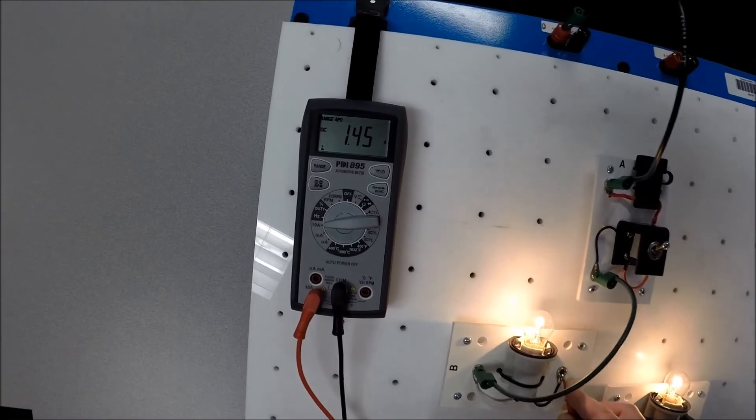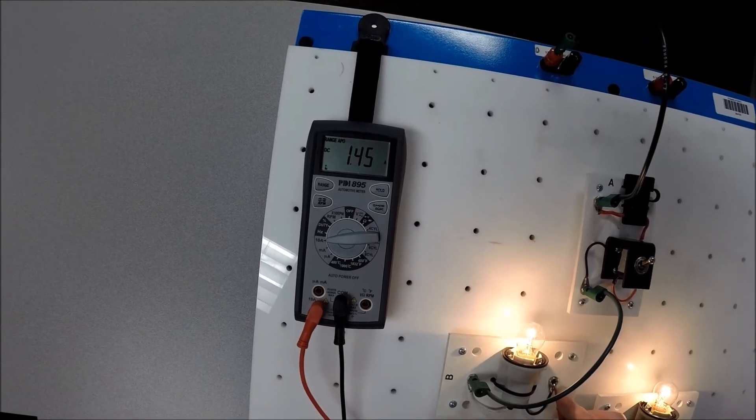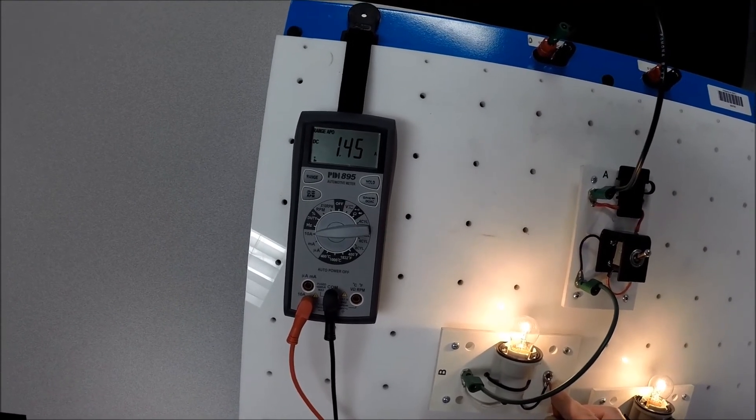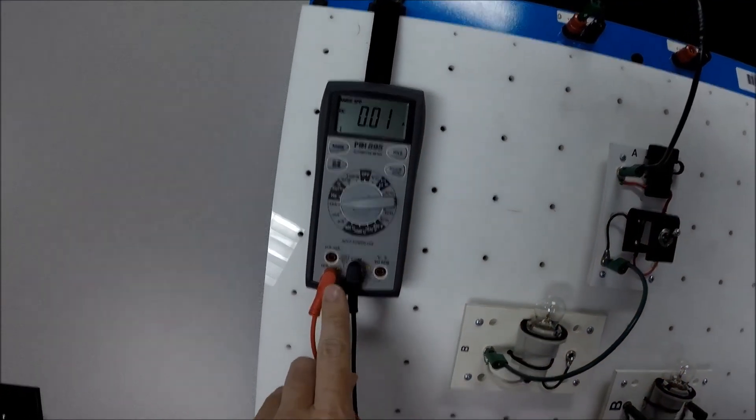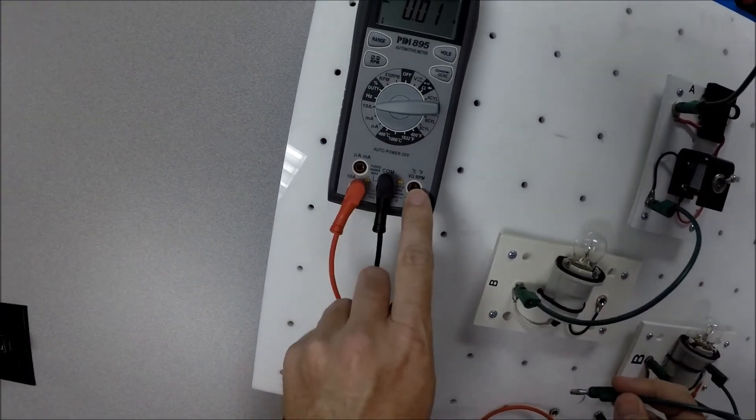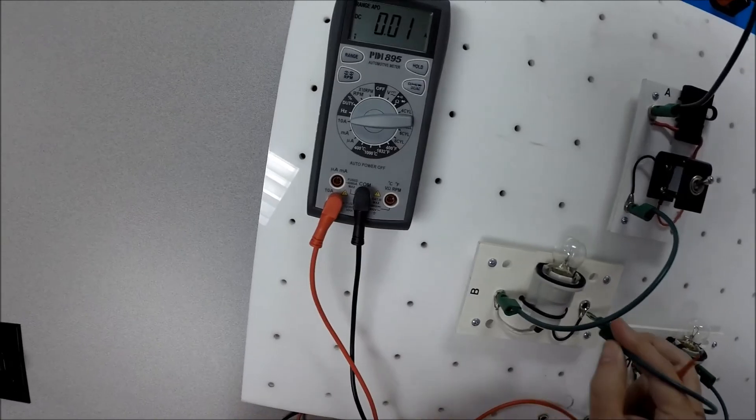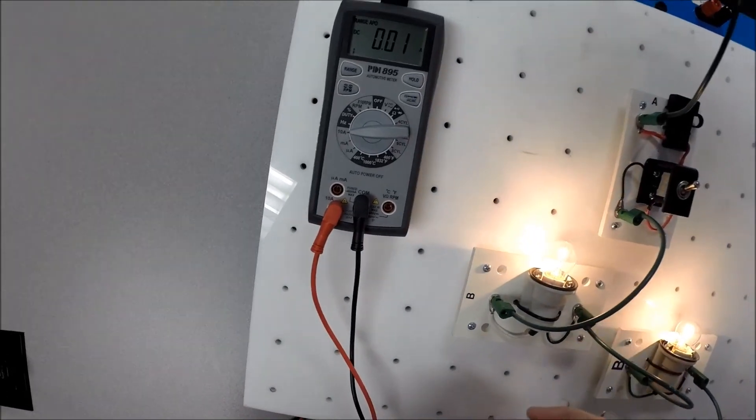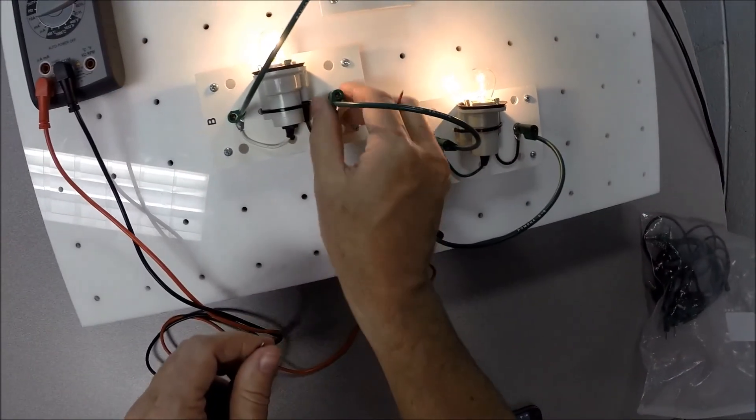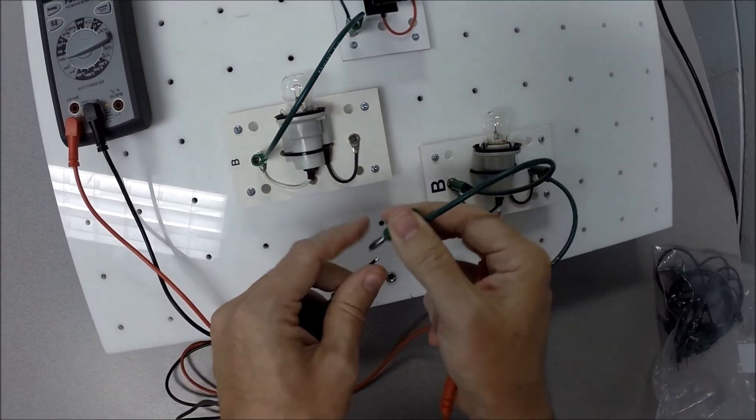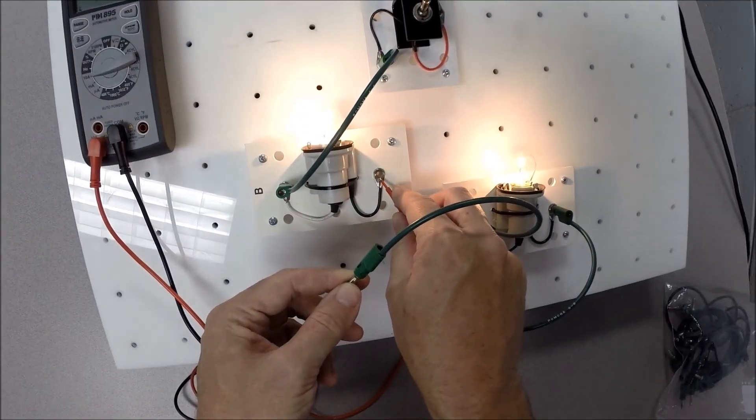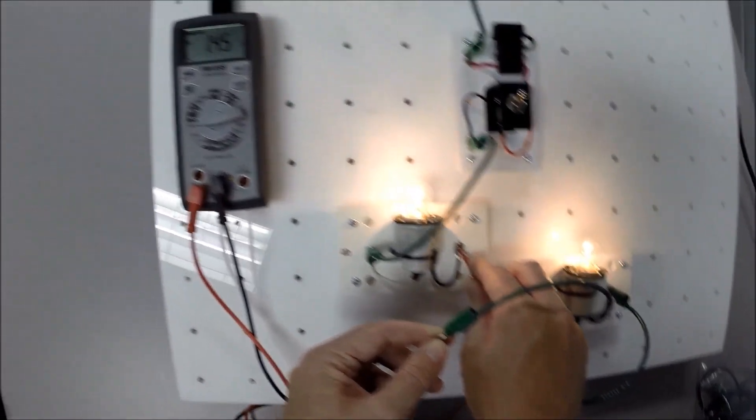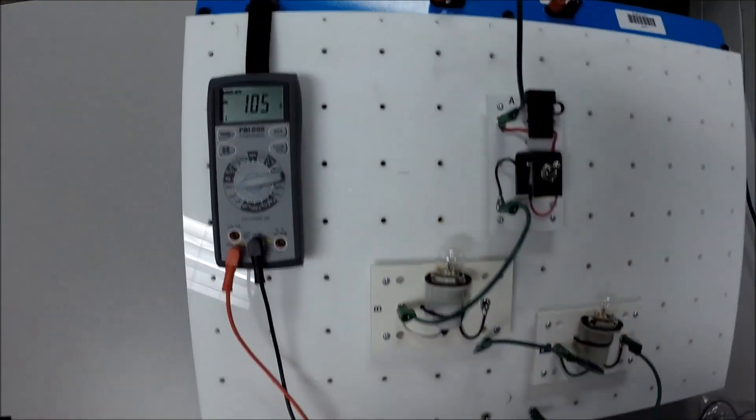So when you're measuring current, remember to select the proper amperage scale on your meter. Remember to move your leads. Make sure that you're not plugged in here. You want to be plugged in there. And then make sure that you actually physically disconnect the circuit and put the meter in series with the circuit in order to get your reading. And that's how we'll measure current.